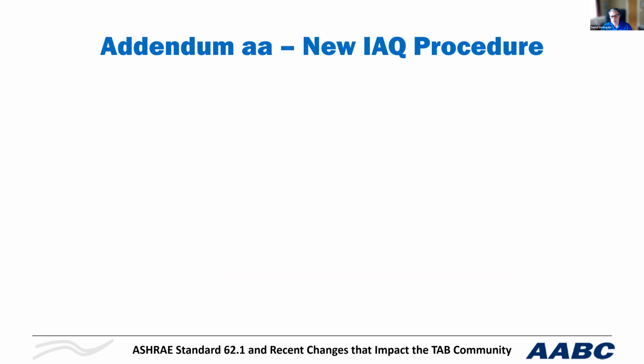Okay. So talking about better air, I had mentioned that the IAQ procedure has existed since 1981, and this is another engineered system. However, there haven't been many prescriptive requirements with respect to the system. So ASHRAE has been taking a look at this for the last 6 years at least, and really taking a hard look and working with the industry, because it's a consensus standard, to come up with a way to make it better. Because one of the challenges is as it was in 1981, today, there is the trend to say that, well, if I use the IAQ procedure, then I can reduce the amount of outside air that you would have in a ventilation rate procedure to save energy.